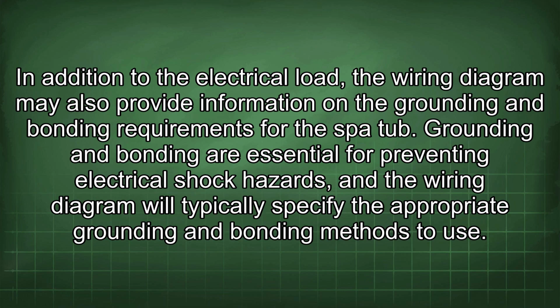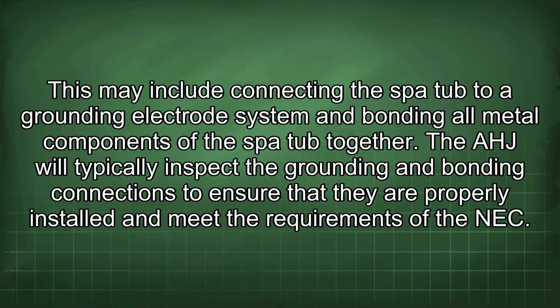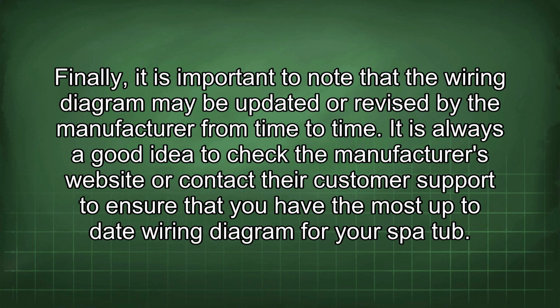Grounding and bonding are essential for preventing electrical shock hazards, and the wiring diagram will typically specify the appropriate grounding and bonding methods to use. This may include connecting the spa tub to a grounding electrode system and bonding all metal components of the spa tub together. The AHJ will typically inspect the grounding and bonding connections to ensure that they are properly installed and meet the requirements of the NEC. Finally, it is important to note that the wiring diagram may be updated or revised by the manufacturer from time to time. It is always a good idea to check the manufacturer's website or contact their customer support to ensure that you have the most up-to-date wiring diagram for your spa tub.